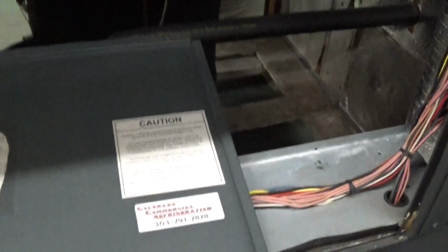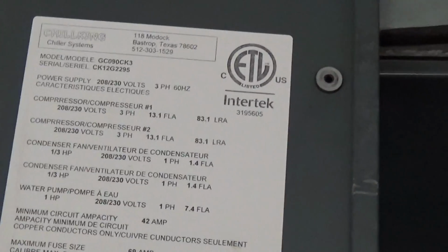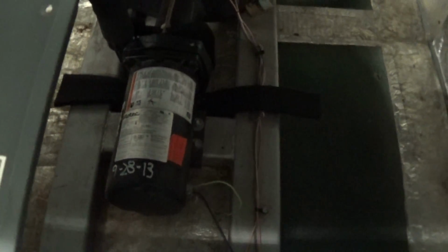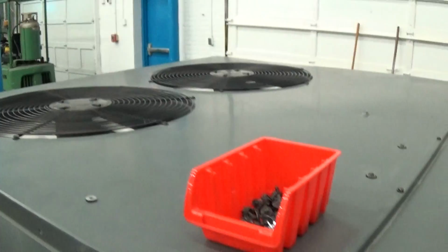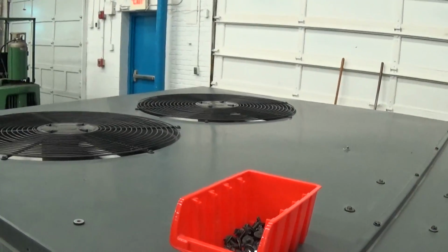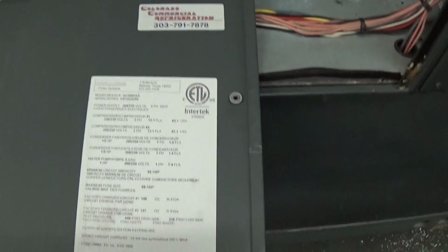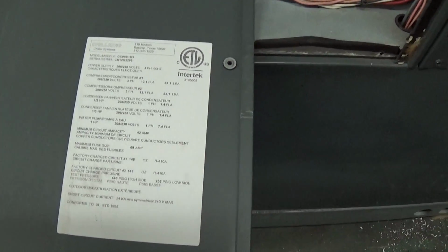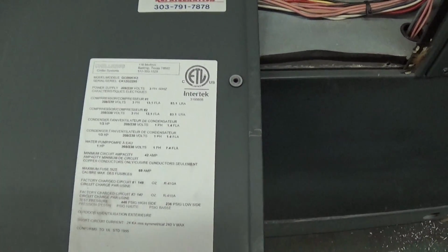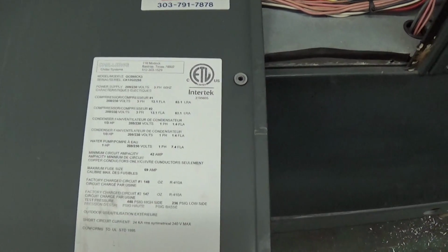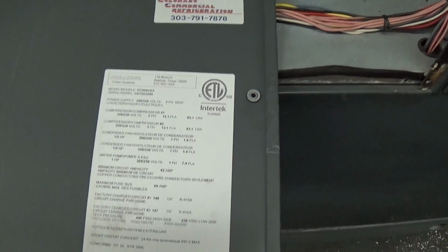So this is a 3-phase unit. It is phase dependent. However, you need to be careful when you start these up and be aware that the pump is a single-phase pump and the fans are single-phase fans. So the main thing you have to be very careful of is to have your HVAC technician confirm that the phase rotation is correct on the 3-phase compressors.